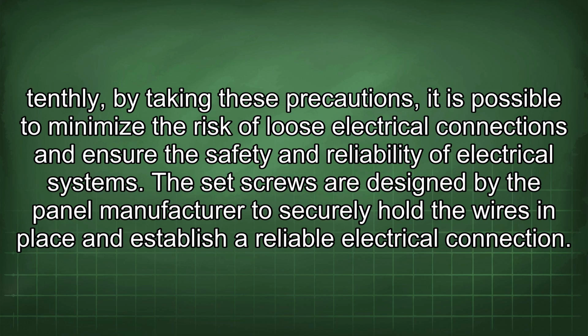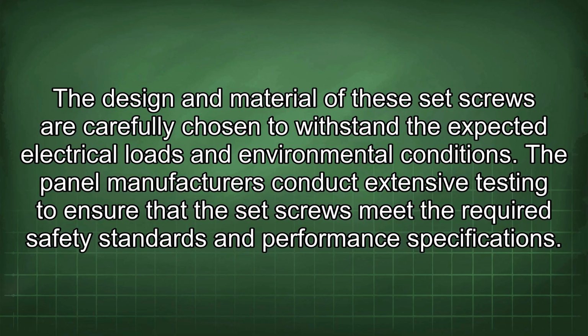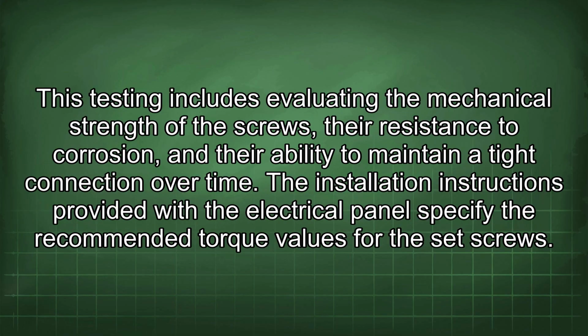The set screws are designed by the panel manufacturer to securely hold the wires in place and establish a reliable electrical connection. The design and material of these set screws are carefully chosen to withstand the expected electrical loads and environmental conditions. The panel manufacturers conduct extensive testing to ensure that the set screws meet the required safety standards and performance specifications. This testing includes evaluating the mechanical strength of the screws, their resistance to corrosion, and their ability to maintain a tight connection over time.